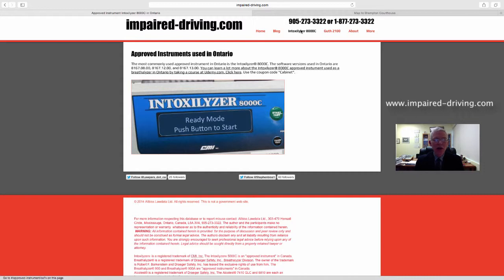As you will read in the blog at www.impaireddriving.com, 0, for purposes of the subject tests and for purposes of the calibration checks, floats. 0 in the instrument's electronics changes frequently depending on ambient conditions. Ambient conditions in the breath room can include ethyl alcohol, that's drinking alcohol, floating in the air, an interferent, that's a substance that behaves in some ways similar to ethyl alcohol, an interferent floating in the air, electrical interference in the power supply, or radio frequency interference in the breath room air.